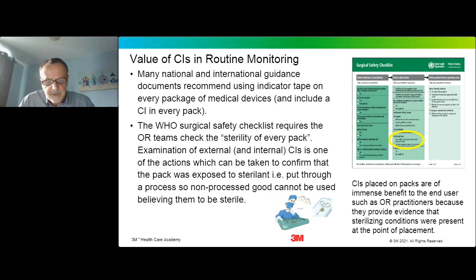So let's now move on to standards for autoclave tape itself. Well, believe it or not, there are no internationally agreed standards specifically written for autoclave tape as a whole. EN ISO 11140 Part 1 describes the performance requirements for the indicator ink, which is printed on the autoclave tape. But this does not extend to cover other attributes of the product, such as how well it sticks to surfaces. I should point out that the British Standards Institute published a standard some years ago, in 1997, which did actually discuss tests for adhesion, along with tests and requirements for the colour change on the indicator tape.